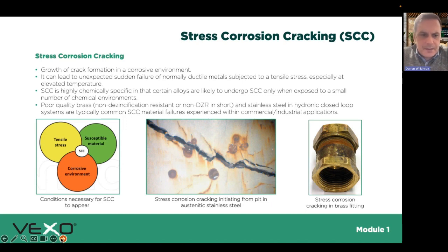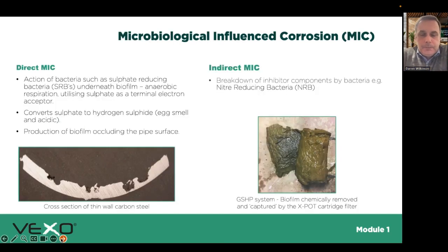Whereas now, there is the EN standard for brass to be dezincification resistant. So a much higher quality and a lot less alloys in there, like zinc, for example, that would normally be stripped out by the ammonia, leaving porous copper. I think this is going to start showing its head more now that we move to much lower operating temperatures, but this is another form of corrosion called microbiologically influenced corrosion, MIC.